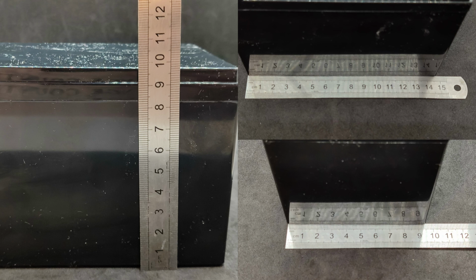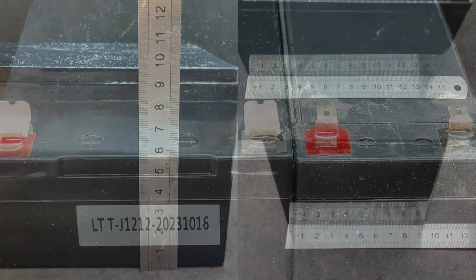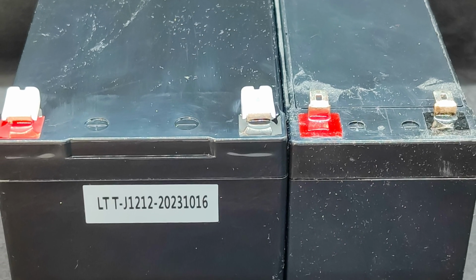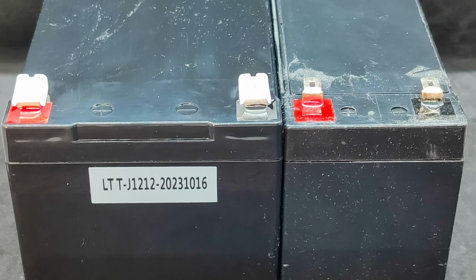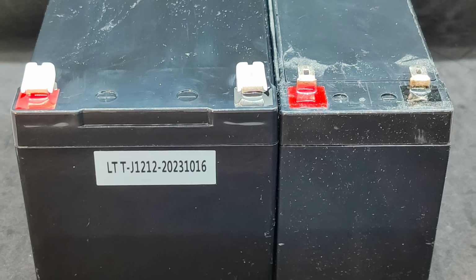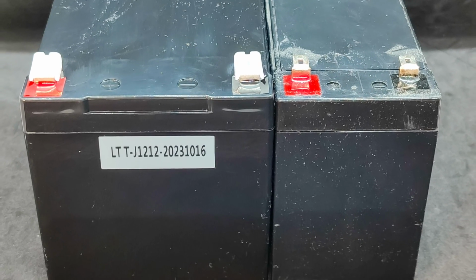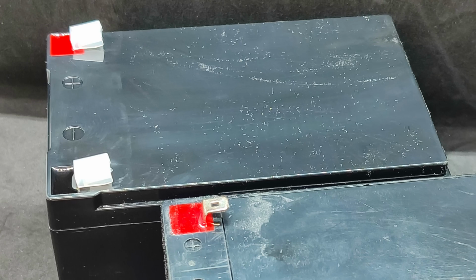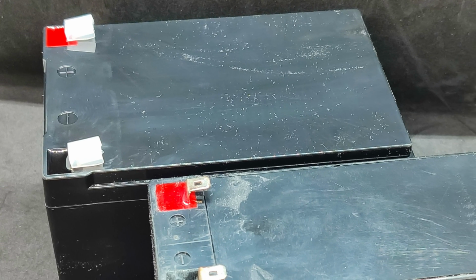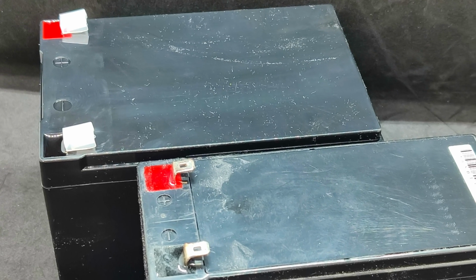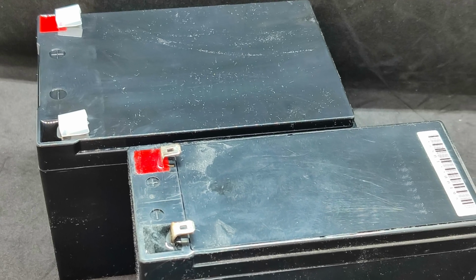But, as you can see in this photo, its width is clearly greater than those batteries used in simple household uninterruptible power supplies. Here's how they look in comparison. The thickness of the lead-acid battery that was installed in the UPS is 65 millimeters. The length and height match. The contacts for connecting to the uninterruptible power supply are also identical. The connectors fit, so there's no need for any modifications.